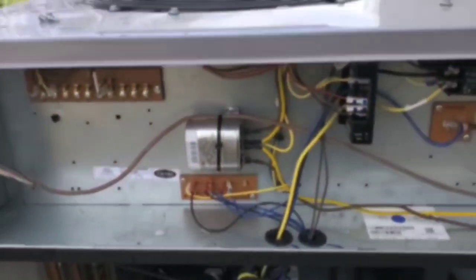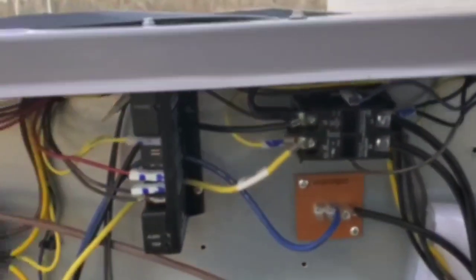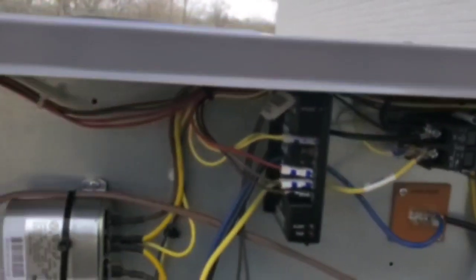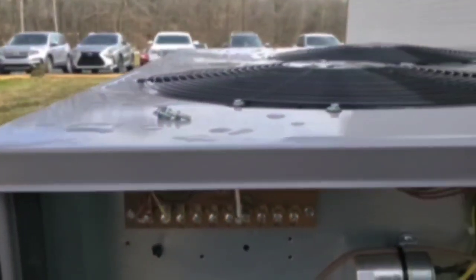So this is a commercial 10-ton condensing unit. Usually these are hooked to with a contactor in it. So we got a transformer here, a little phase monitor, contactor. And the way it's supposed to work is you connect between R and Y1 there on that terminal block, and it activates the condensing unit.